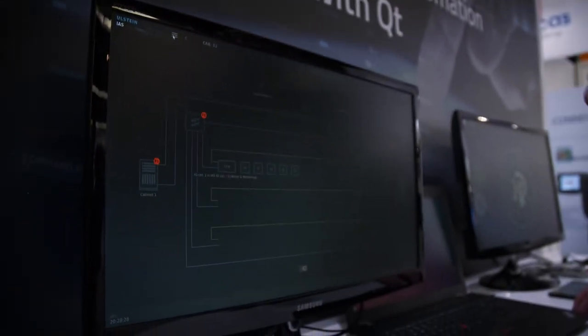This is all automatically drawn by the configurator. What we normally do is get in the IO list and the component list when doing an automation integration. We have our own tools to pick from a database of components like tanks, pumps, valves, bus breakers, diesel generators, motors, and engines. Within that tool, we configure everything together, and when we deploy, we auto-generate a lot of XML files for all the visual objects.